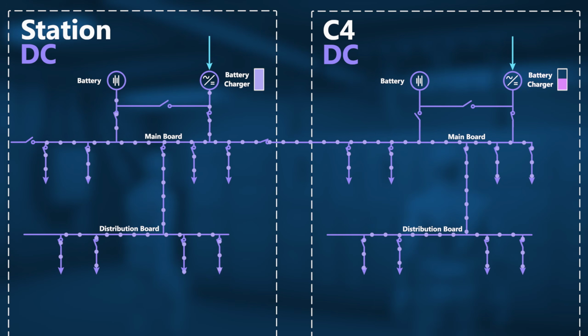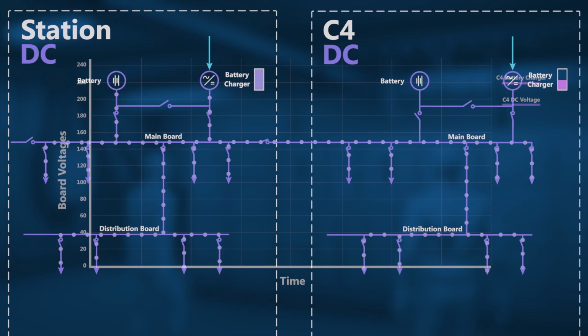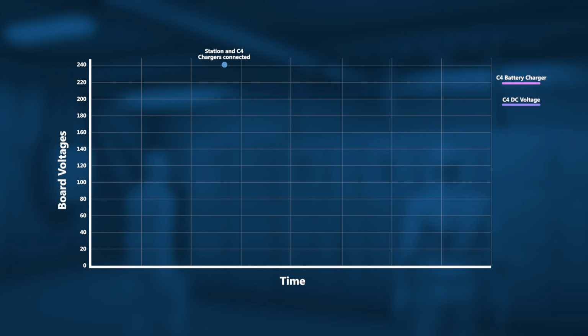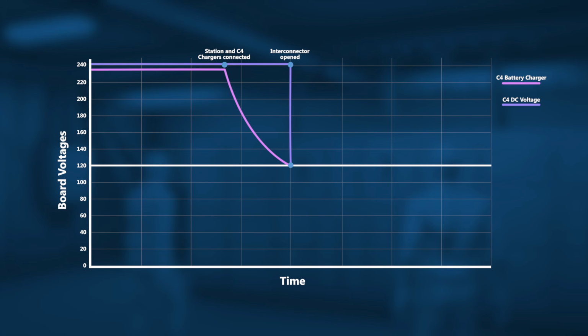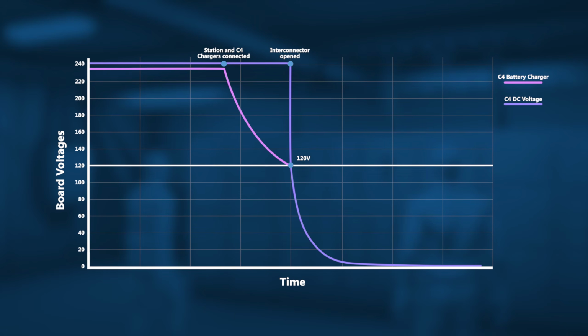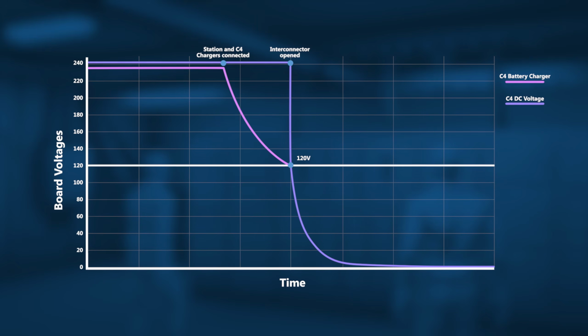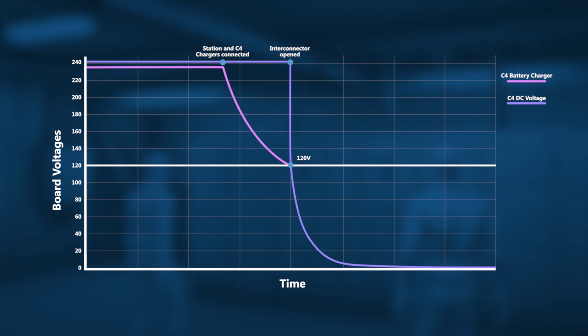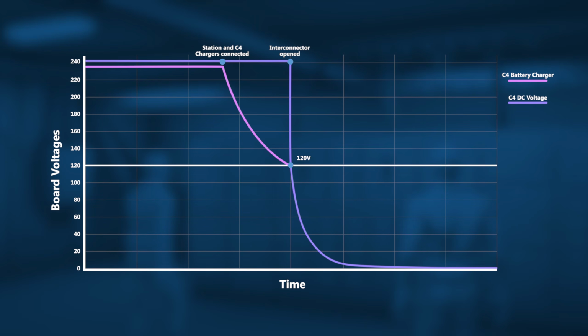This is precisely what happened in the C4 charger. In the 74 seconds between the 2 chargers being connected to the same system and the interconnector being opened, the voltage in the C4 charger had decayed to nearly half of what was required. So the instant the interconnector was opened, the voltage in the C4 DC system collapsed to the level of the C4 charger's internal voltage, just 120 volts. And it was the specific nature of this collapse that led to the loss of AC power as well. But in order to understand how this happened, we need to look at how a mechanism designed to protect the AC system inadvertently led to its loss.